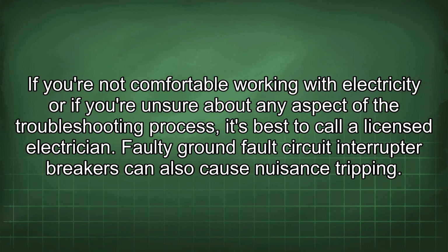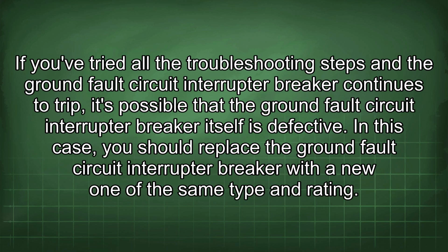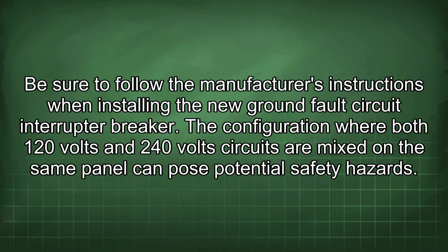Faulty ground fault circuit interrupter breakers can also cause nuisance tripping. If you've tried all the troubleshooting steps and the ground fault circuit interrupter breaker continues to trip, it's possible that the ground fault circuit interrupter breaker itself is defective. In this case, you should replace it with a new one of the same type and rating. Be sure to follow the manufacturer's instructions when installing the new ground fault circuit interrupter breaker.